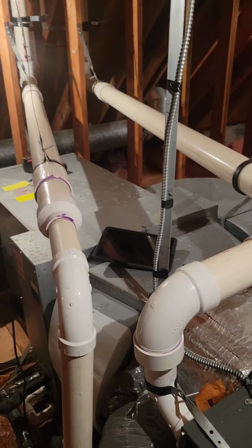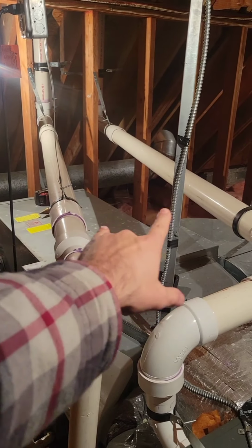Obviously, this is considered an unconditioned space. We have an unconditioned space. It can be prone to freezing. Example, you put a 90% unit in the attic, which creates condensation. Condensation creates water. Water can freeze if the temperature gets to a certain level, right? So let me see if I can flip this. Okay. My knees. I'm getting old. So you can see they have an intake and exhaust.